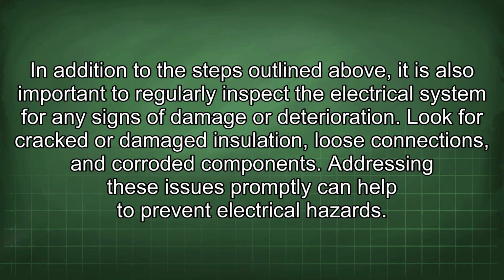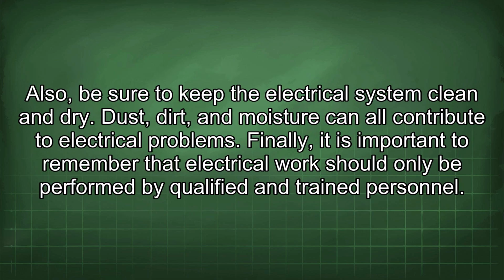In addition to the steps outlined above, it is also important to regularly inspect the electrical system for any signs of damage or deterioration. Look for cracked or damaged insulation, loose connections, and corroded components. Addressing these issues promptly can help to prevent electrical hazards. Also, be sure to keep the electrical system clean and dry. Dust, dirt, and moisture can all contribute to electrical problems.